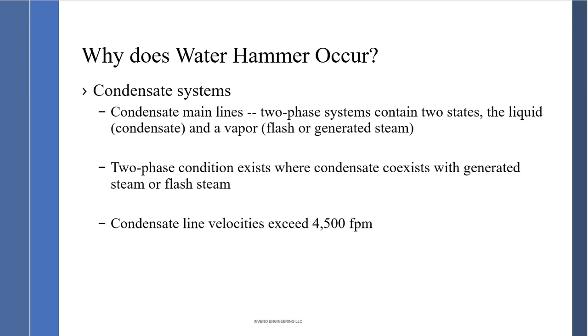Condensate systems. Two-phase systems contain 2 states, a liquid and condensate, and a vapor, which is flash or generated steam. And what was meant by generated steam, steam that's flowing from a failed steam trap or a bypass valve into the condensate system. The two-phase condition exists when condensate coexists with the generated or flash steam. Condensate line velocities can never exceed 4,500 feet per minute. So the thing is that at steam lines, we go up to 10,000 feet per minute. But at condensate lines, we only want to be at 4,500 feet per minute.